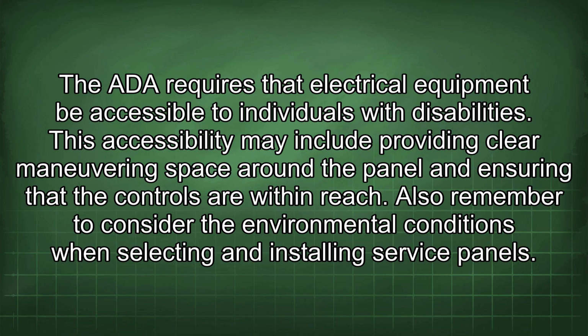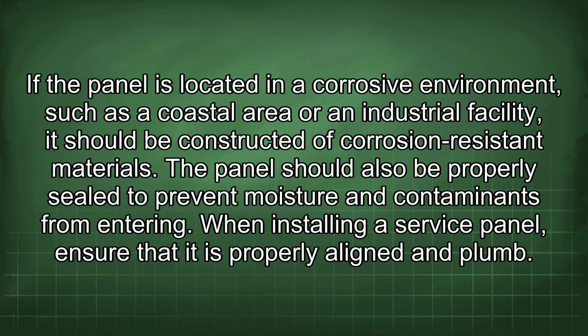Also remember to consider the environmental conditions when selecting and installing service panels. If the panel is located in a corrosive environment, such as a coastal area or an industrial facility, it should be constructed of corrosion-resistant materials. The panel should also be properly sealed to prevent moisture and contaminants from entering.